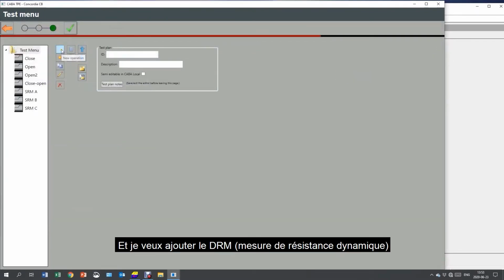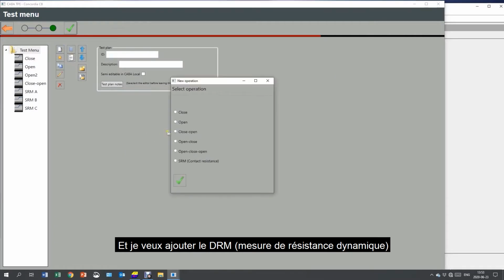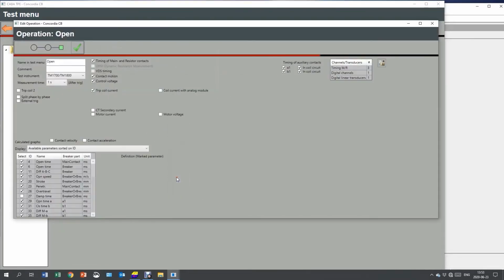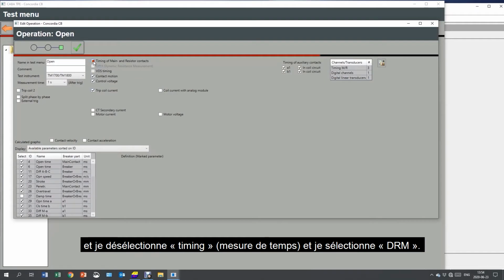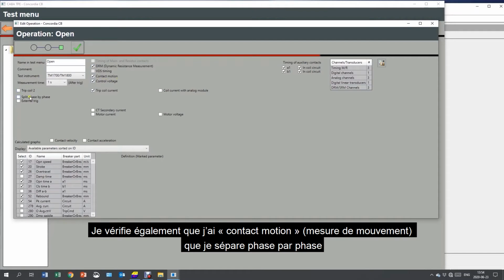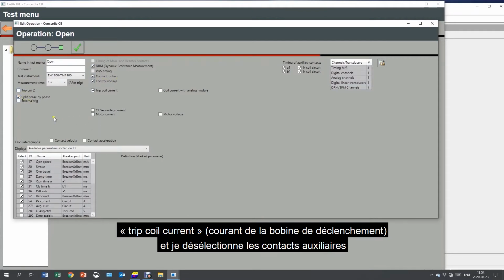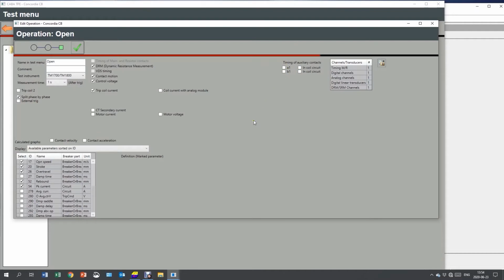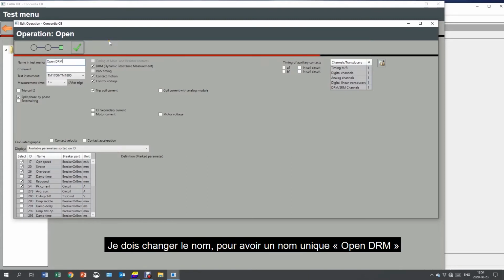And I want to add the DRM, dynamic resistance measurement. By that, I select Open, and I deselect the timing and select the DRM. I also checked contact motion. That's I split phase by phase, trip coil current, and I remove the auxiliary contacts. I need to change the name to have a unique name, Open DRM.